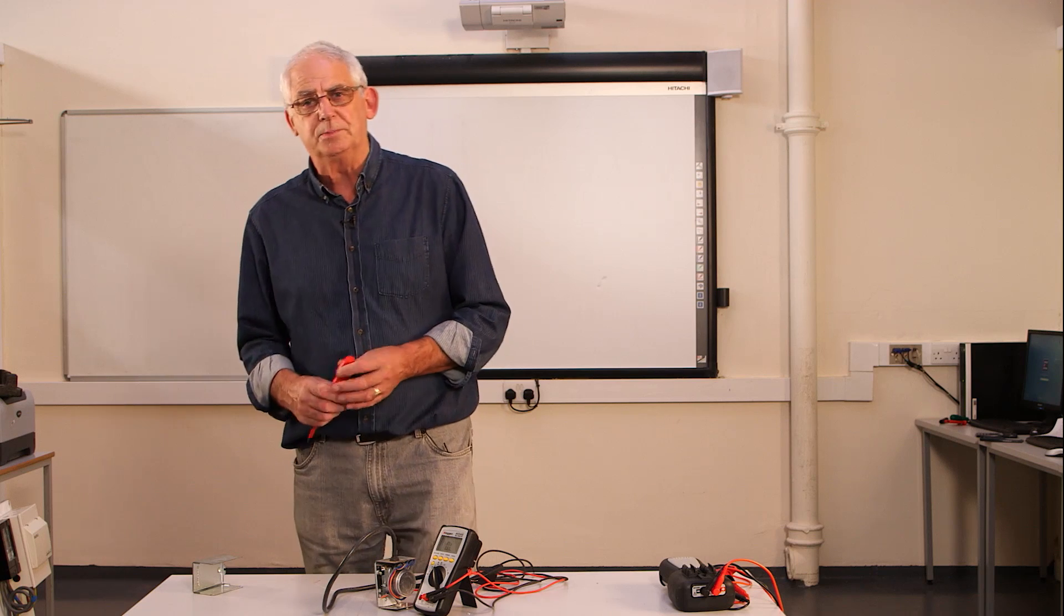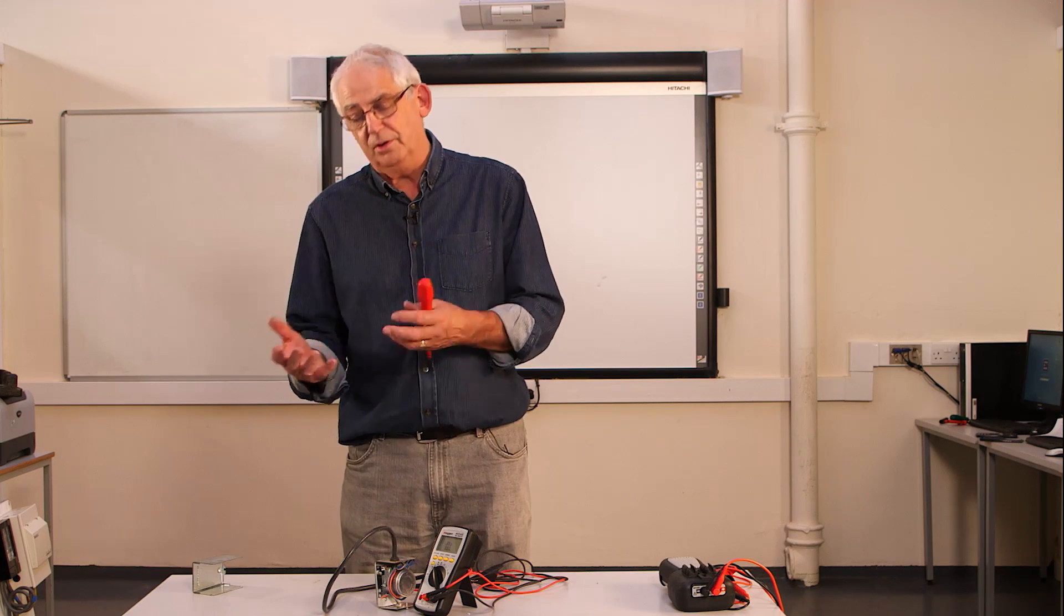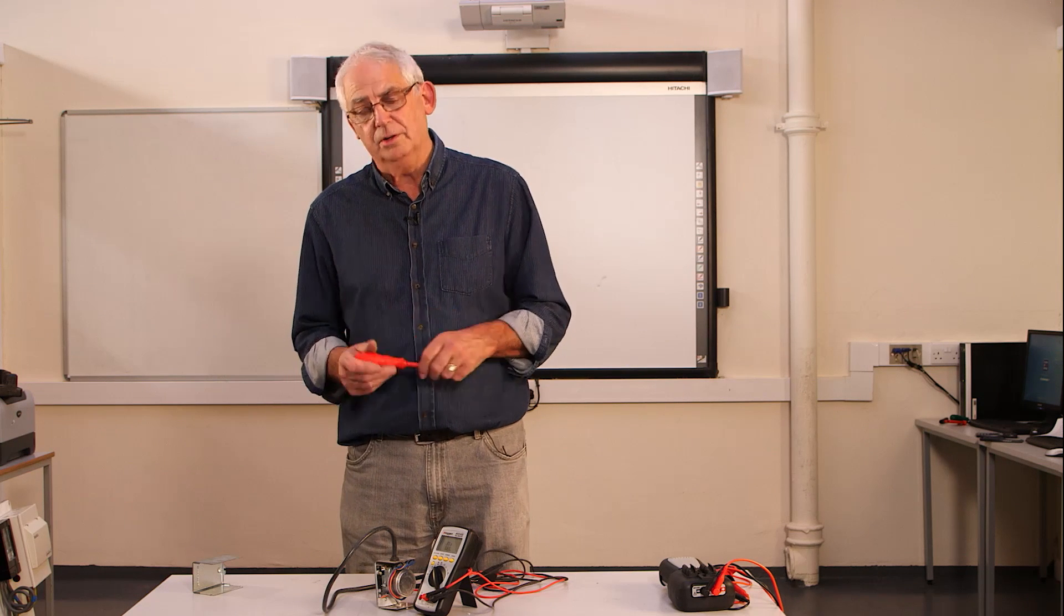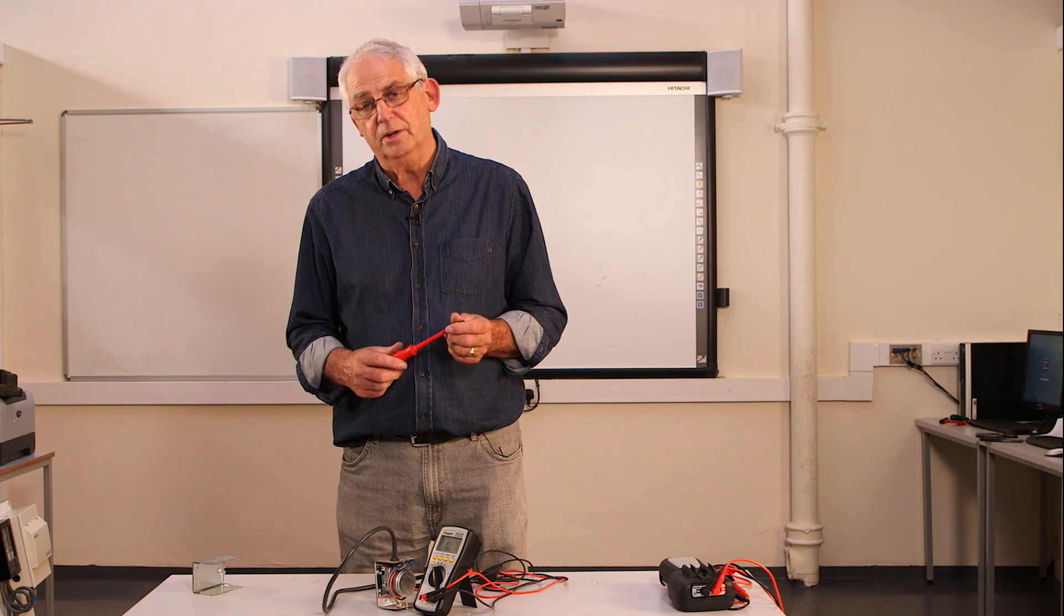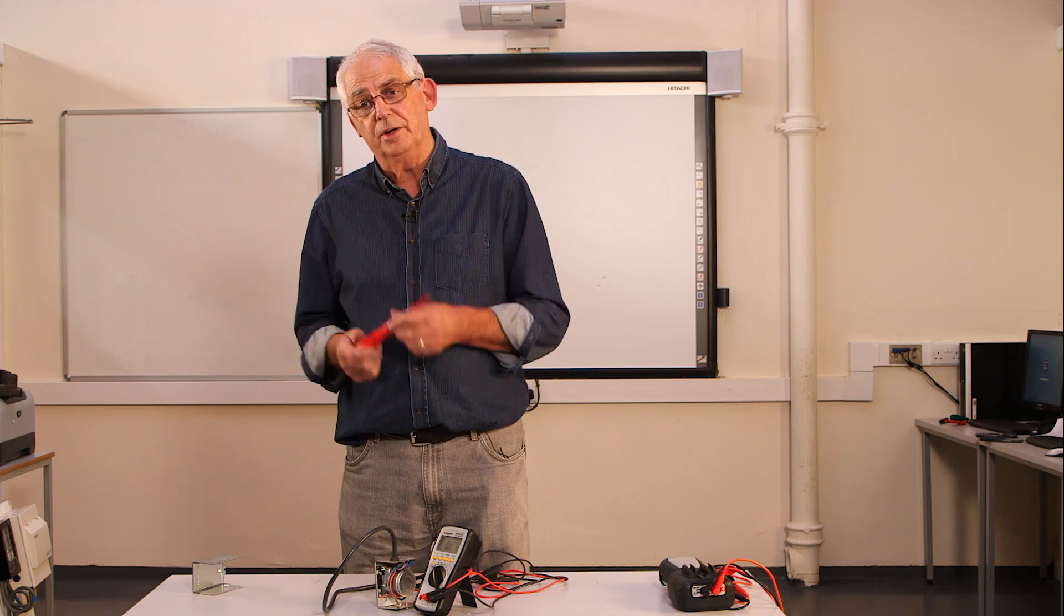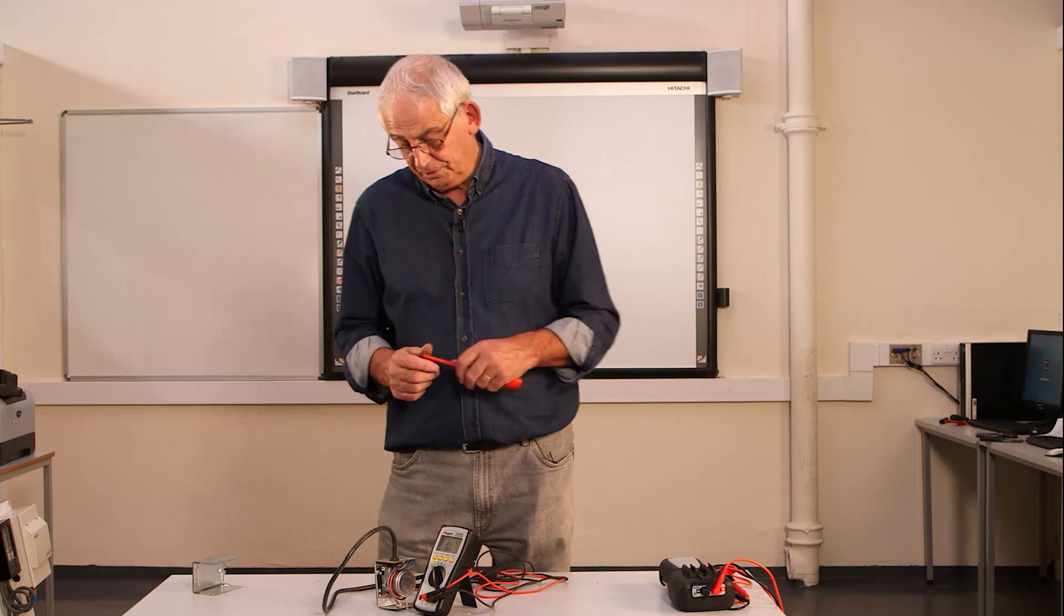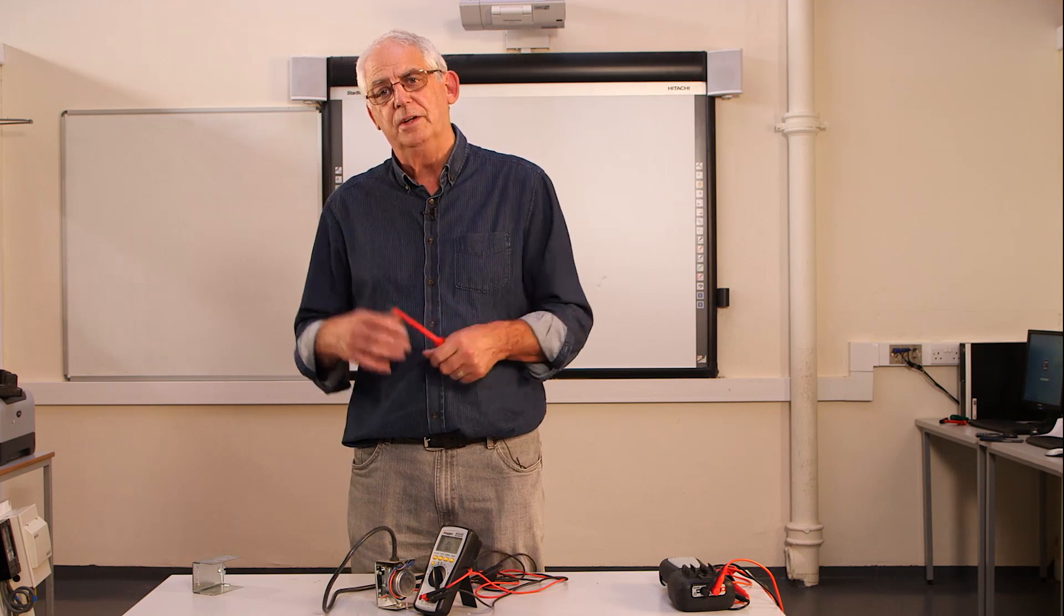Just a nice simple process but it will actually tell you whether or not the micro switch is serviceable, whether or not the motorized valve is serviceable. Sometimes the micro switches stick and they just want freeing up. Lots of different little things that you need to do but if you can just learn the basics of this sort of stuff, it makes life so much easier.